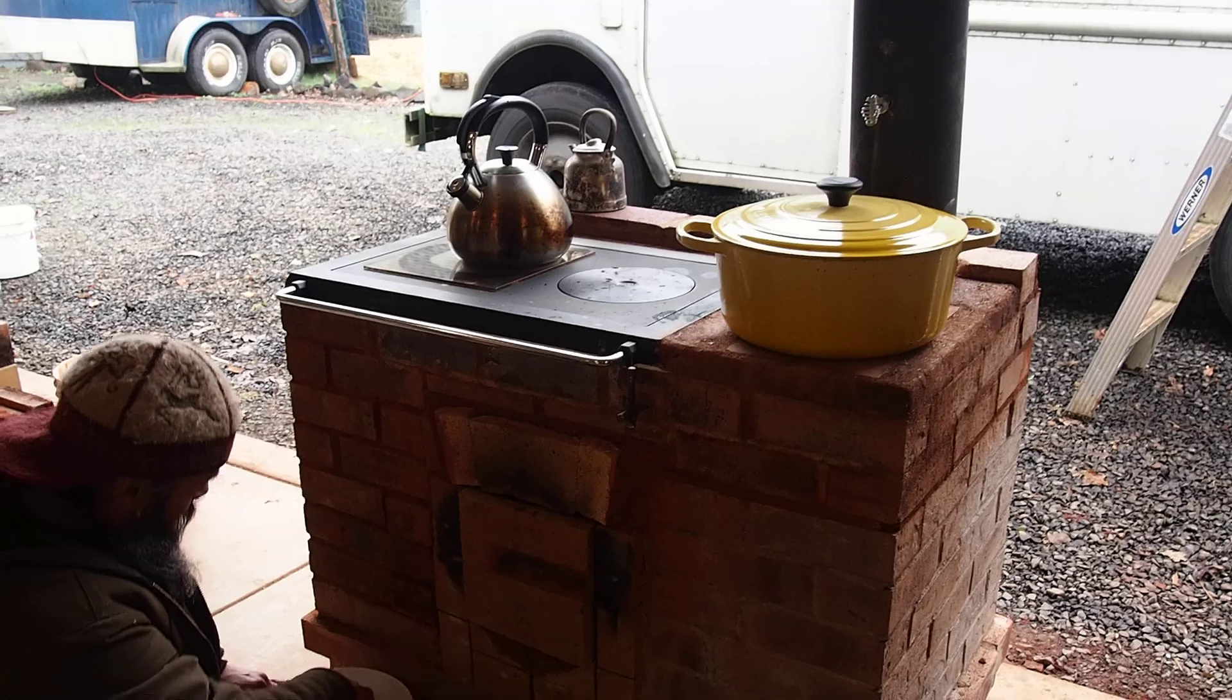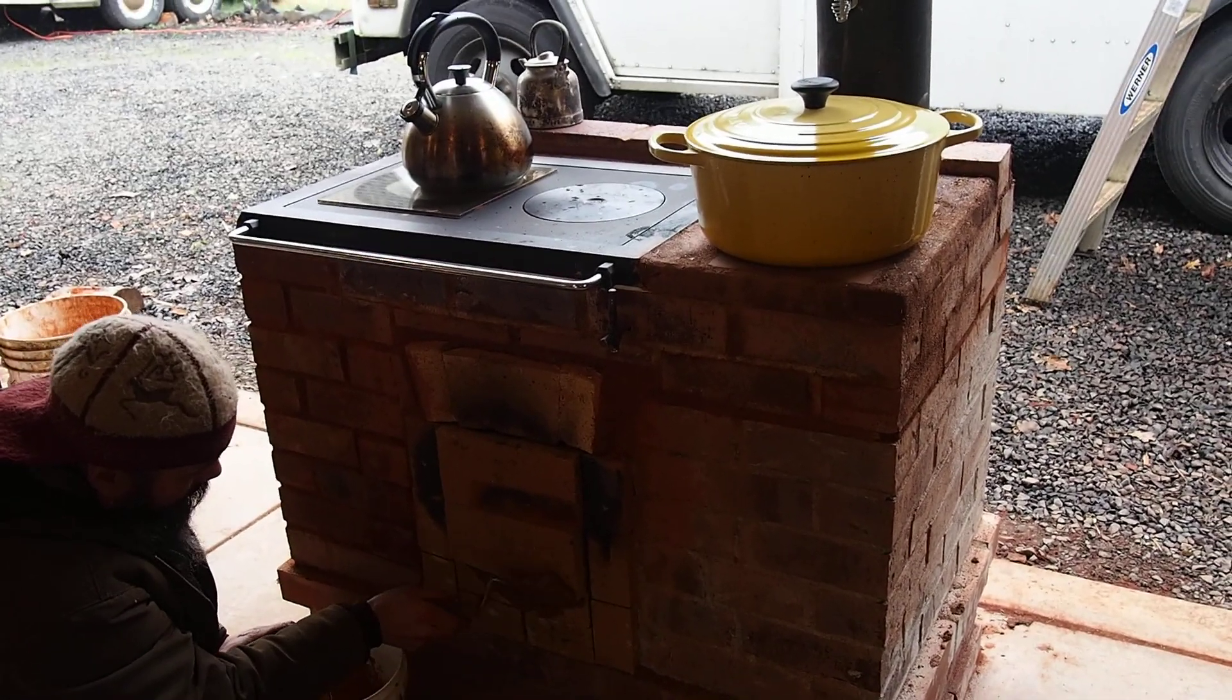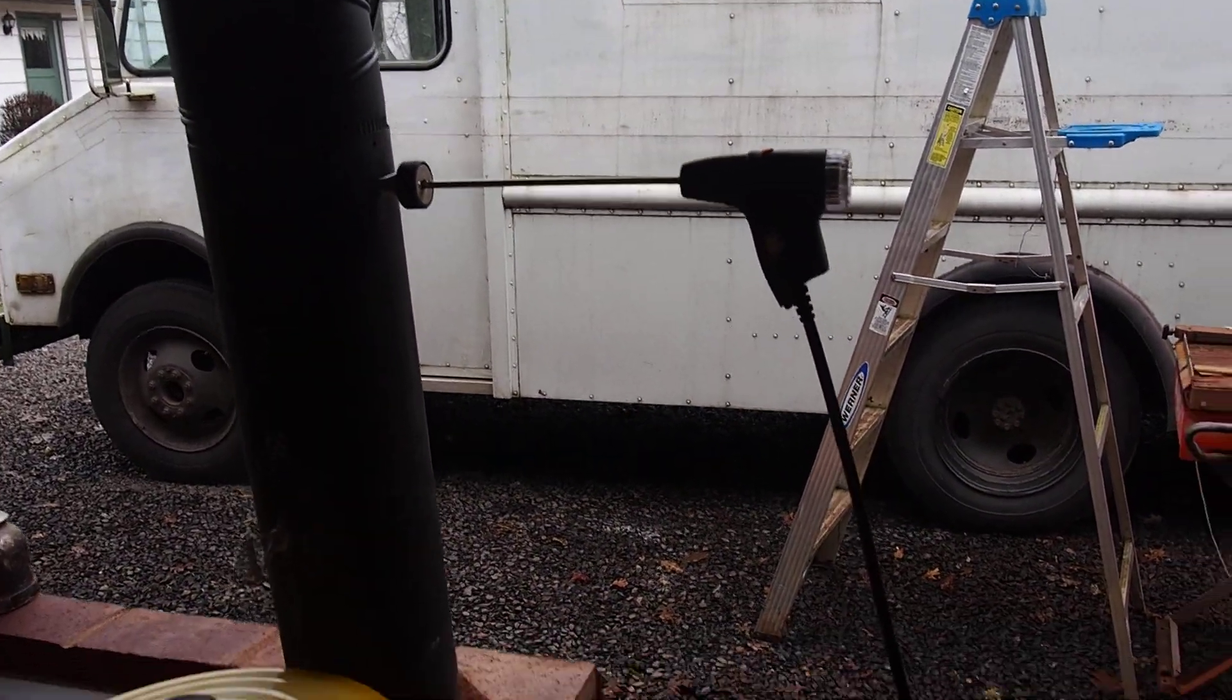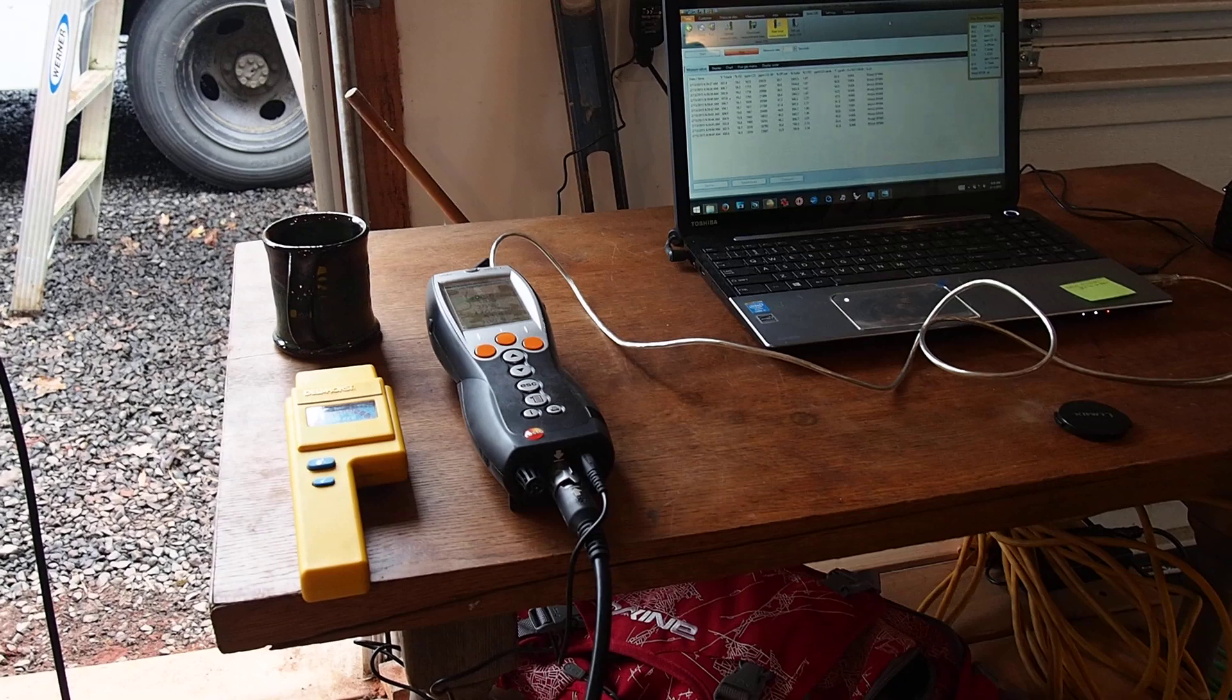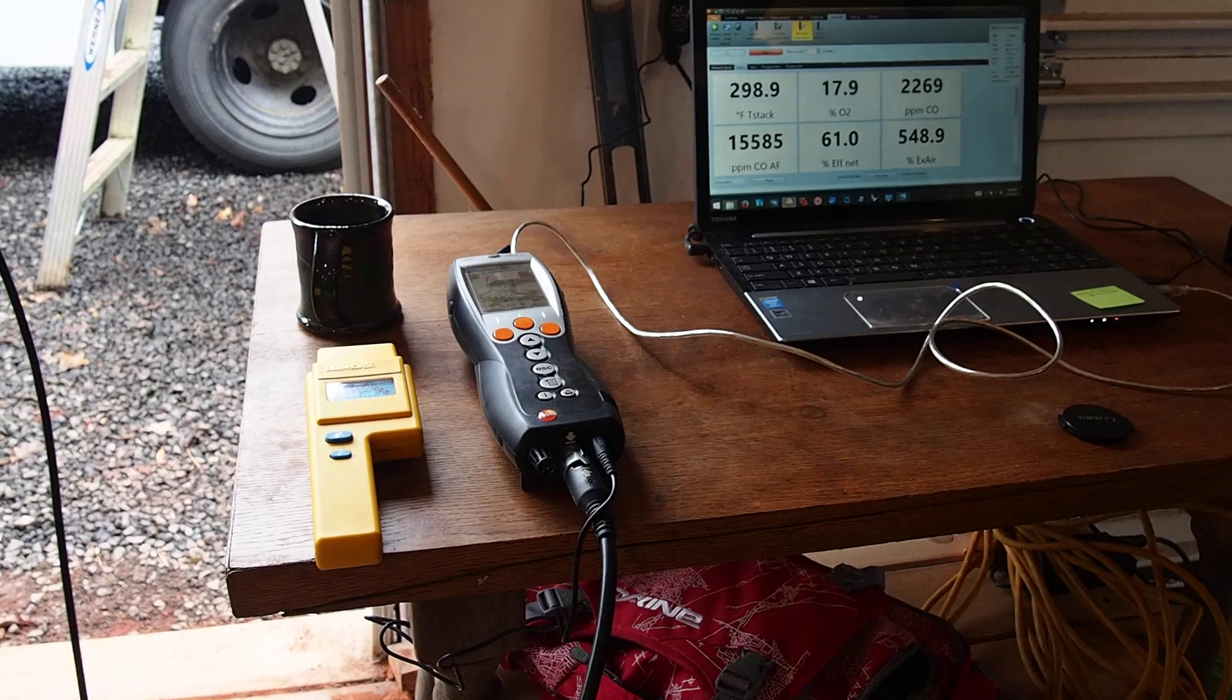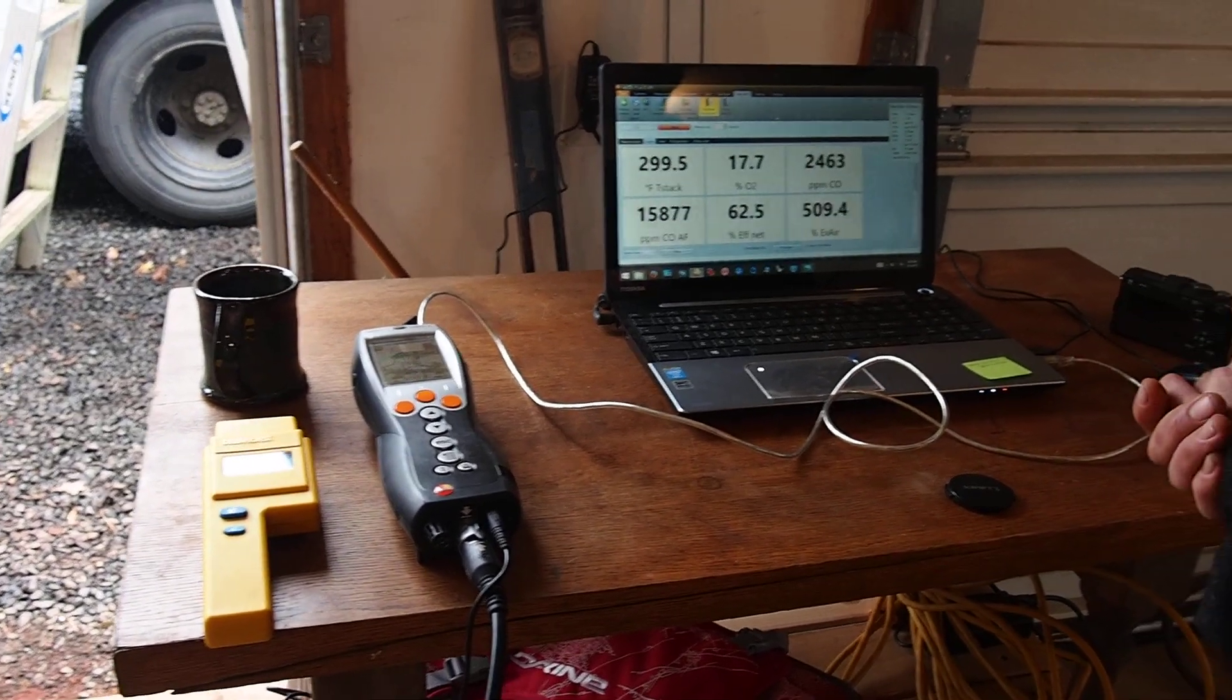What's happening here is we just put a fuel load in and we have fairly sophisticated, almost consumer level electronics that are measuring the carbon monoxide and overall efficiency having to do with stack temperatures.